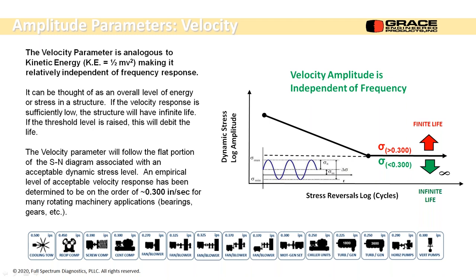So if I have a horizontal pump, my value is 0.29 inches per second. So if I operate below 0.29 inches per second, I'll have infinite life. Okay. Doesn't matter what frequency, it's flat across the frequency range. There's no slope to that line. If I operate above 0.3 inches per second, or above 0.29, I'm going to have finite life. Eventually it's going to fail. So that's my alarm level. If I can stay lower than that, I'll have better outcomes on my machinery.